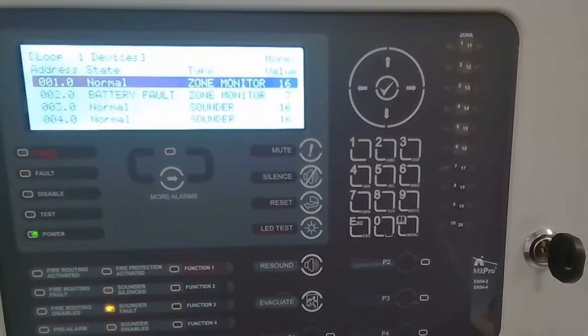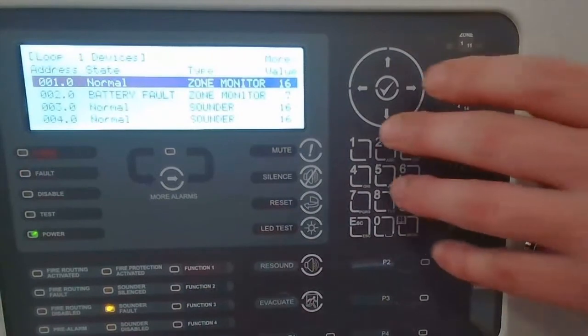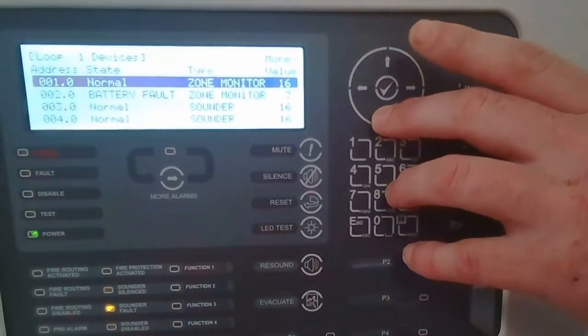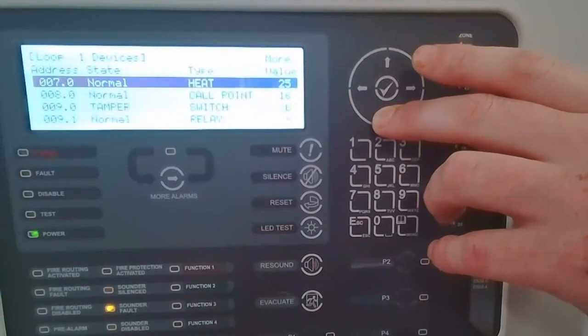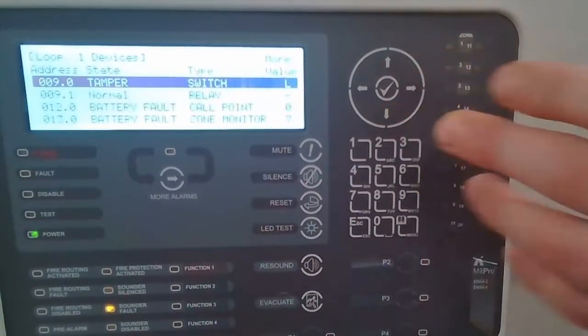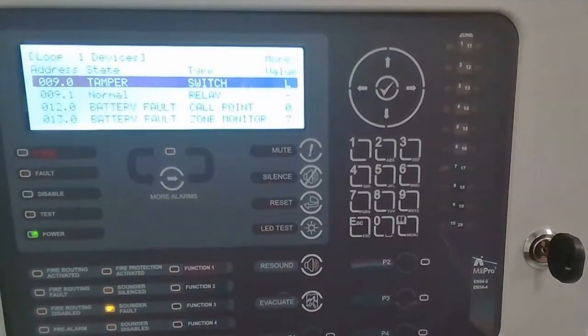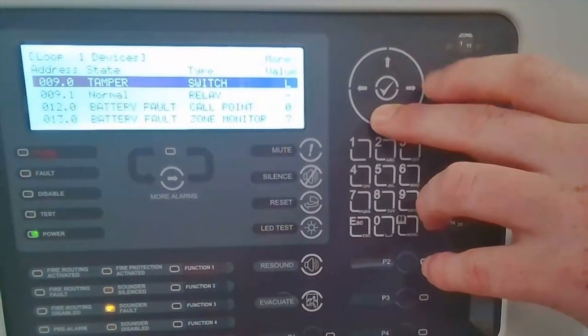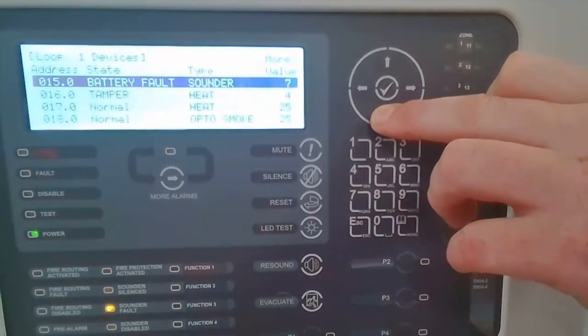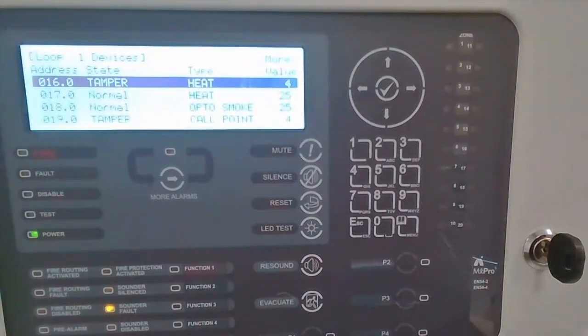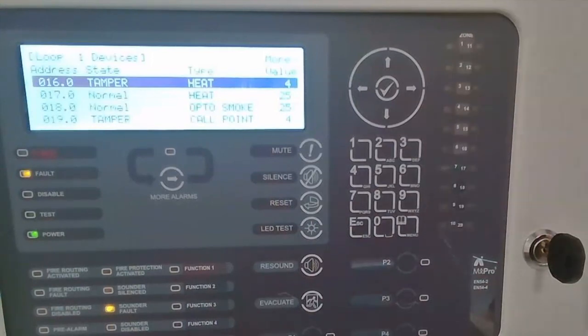Address 2 for example is reporting a battery fault, rather than the previous generic device fault. Scrolling down, there's a tamper message from a device rather than just a device fault. We have actual battery faults and tamper messages being reported from devices — for example, a device may have been removed for the tamper message to show — rather than just the generic device fault message.